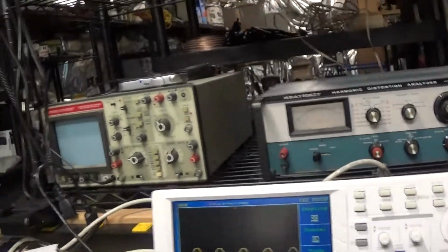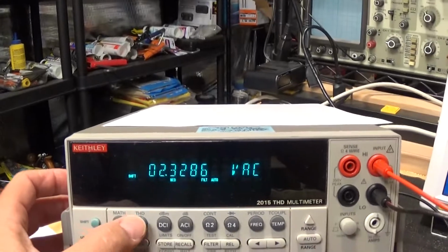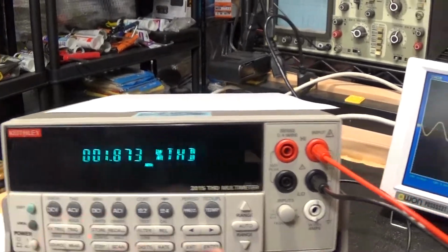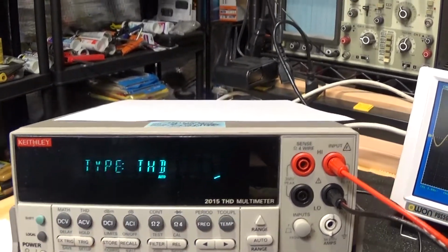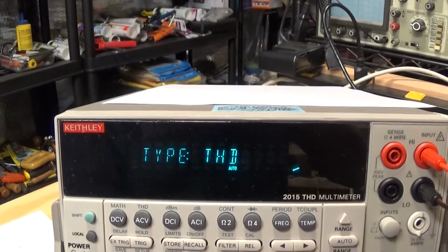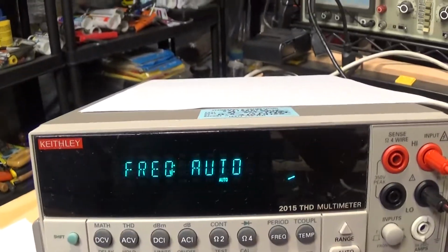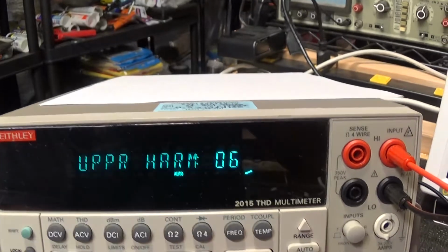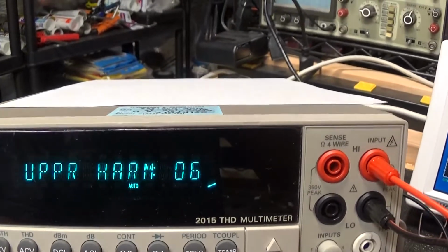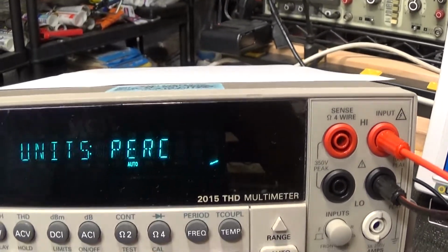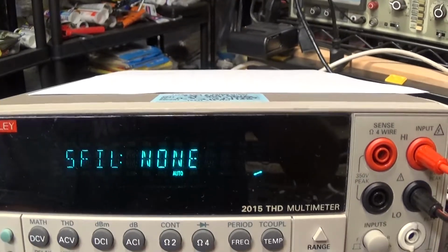Let me do a quick setup here—I'll explain later what I'm doing, but I need this to get a good reading. I'm measuring THD, and it's going to automatically select the fundamental frequency. I want to measure up to 6 harmonics, though I can change that, and I want units in percentage THD.